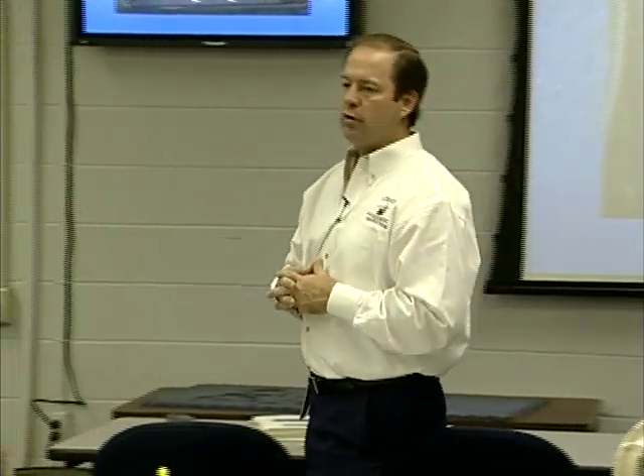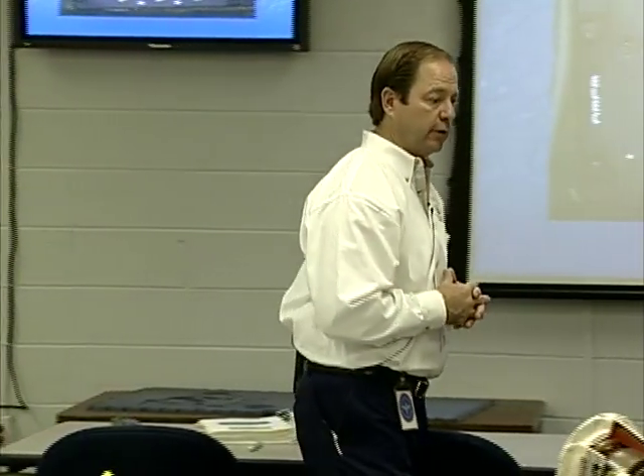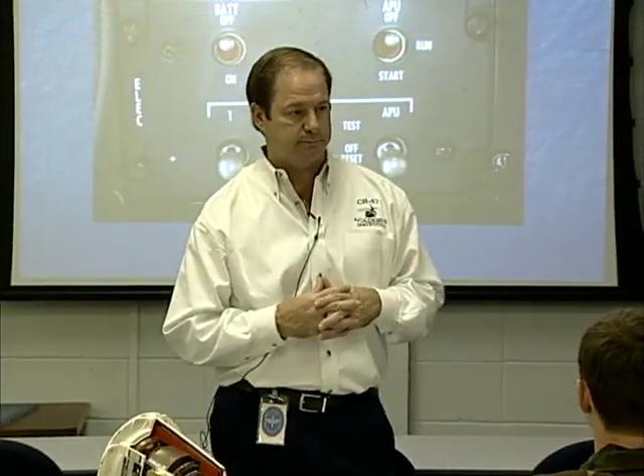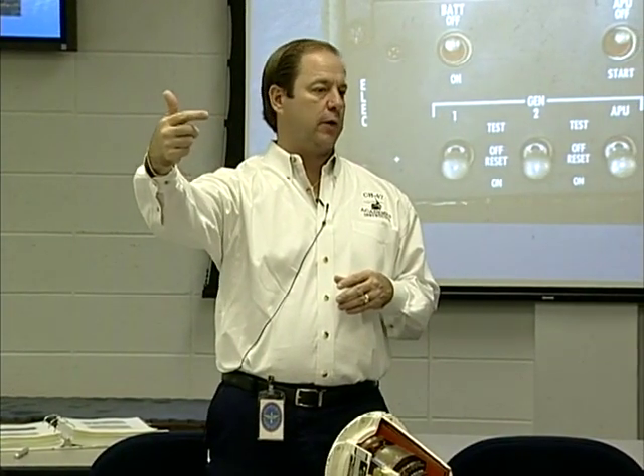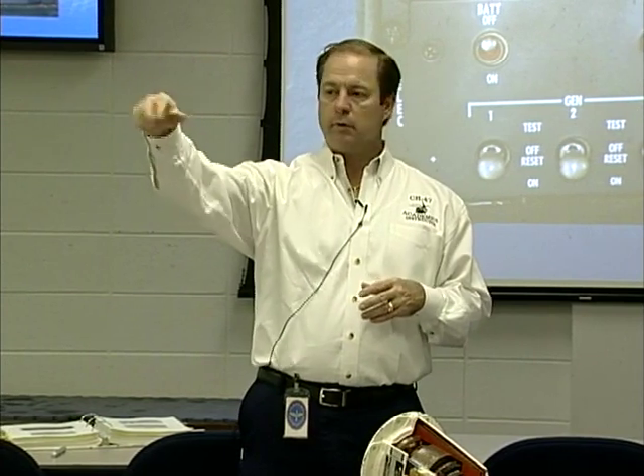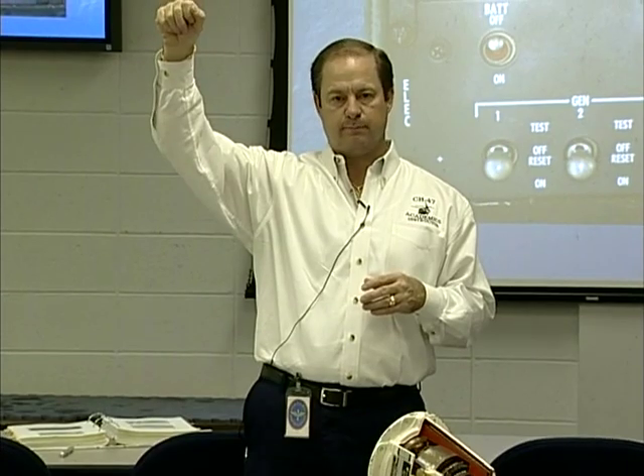When we troubleshoot the generators, in the case of a dual generator failure, it's going to tell me to go to the off reset position. I'm going to be tempted to go to the test position. My main generator off caution capsule was already on, agreed? If I go anywhere other than the off reset position, I go to the test position. What's going to happen in the test position is it's going to test the system for an over voltage, under frequency, and feeder fault. If it senses any of those, how do you think it's going to tell me whether it sensed it or not?